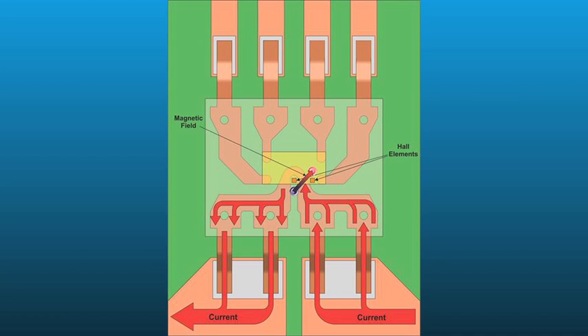One way of dealing with this issue is to add a second Hall plate on the opposite side of the primary current path. When current flows through the primary path, one Hall plate will see a positive magnetic field and the other will see a negative magnetic field. By subtracting the outputs of the two Hall plates, the result is a larger signal still proportional to the current.